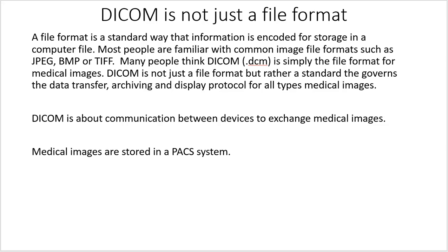DICOM is not just a file format, but rather a standard that governs the data transfer, archiving, and display protocol for all types of medical images. DICOM governs the language and the process by which these images are moved and archived. DICOM is about communication between devices that exchange medical images.